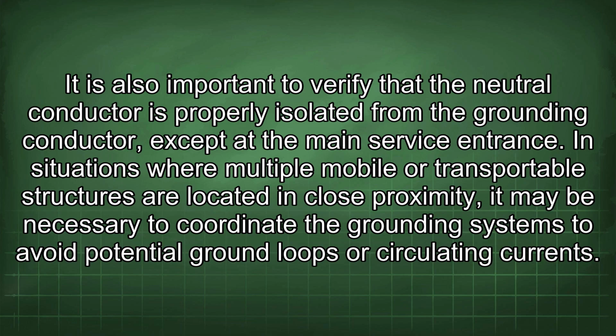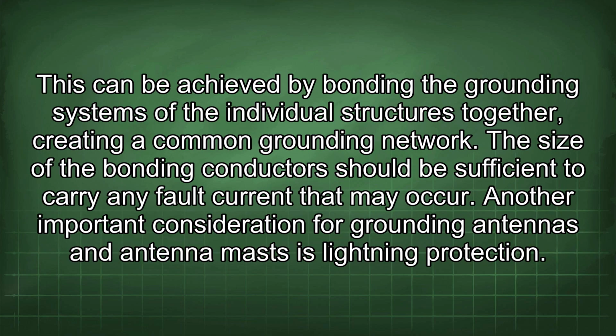In situations where multiple mobile or transportable structures are located in close proximity, it may be necessary to coordinate the grounding systems to avoid potential ground loops or circulating currents. This can be achieved by bonding the grounding systems of the individual structures together, creating a common grounding network. The size of the bonding conductors should be sufficient to carry any fault current that may occur. Another important consideration for grounding antennas and antenna masts is lightning protection.